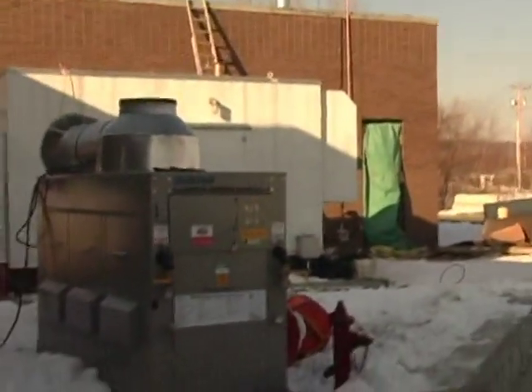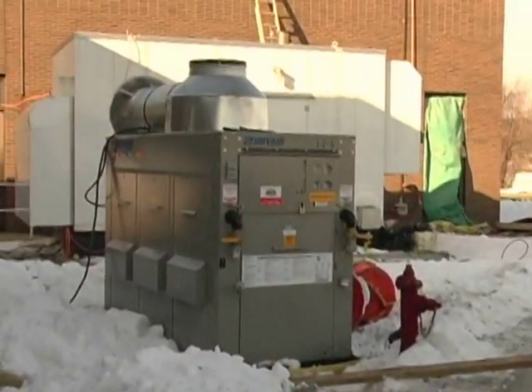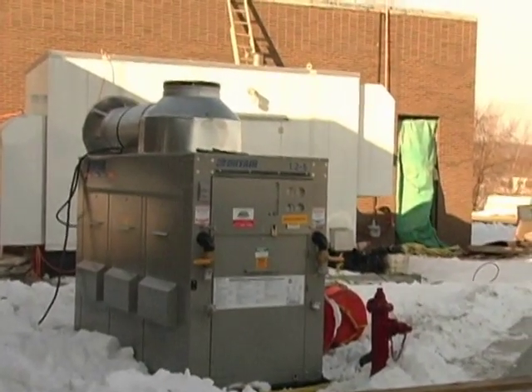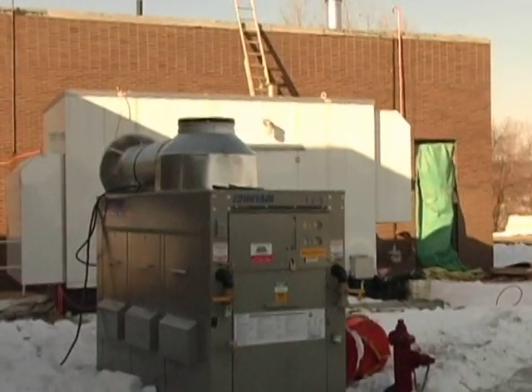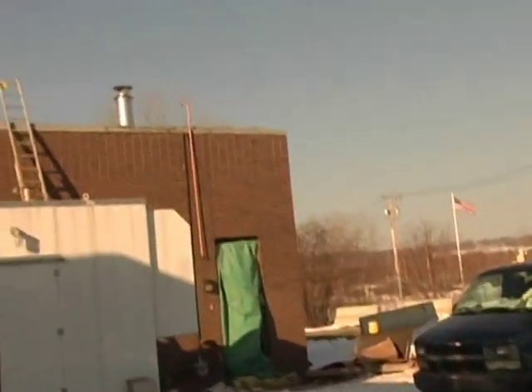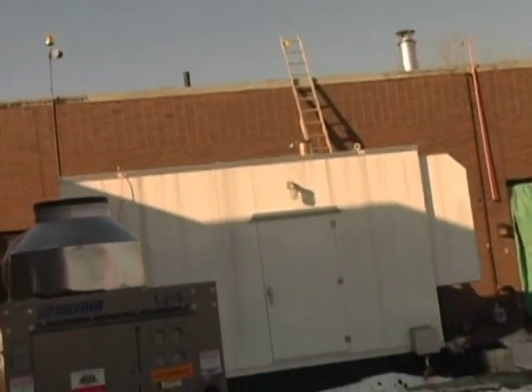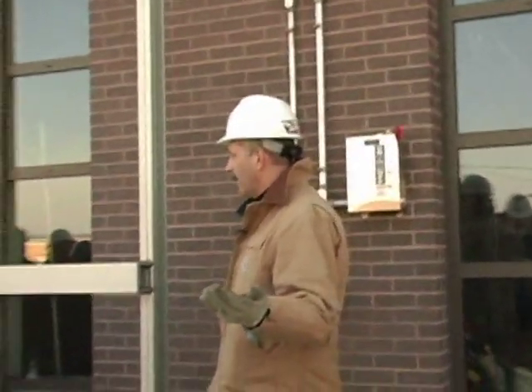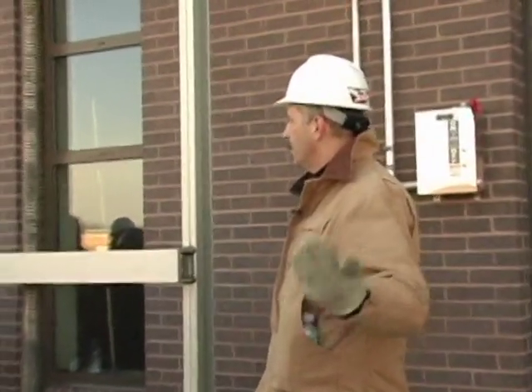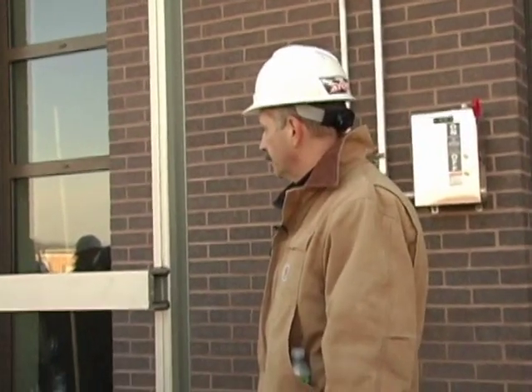Okay, let's take a walk inside. One thing I want to mention before I go in is the emergency generator is located off to my left. That's providing standby power. In the event that you lose utility power to the system, the standby generator will sense the loss of power. The transfer gear is located within the electrical room. We'll take a walk by that on the way through. That will provide emergency, or standby, power to your facility to be able to run your operation if in fact you lose utility power. I believe right now that's been set up for automatic operation, so that if we have a power failure at this point, the generator will come on and provide power to the facility. Okay? Let's take a walk in.